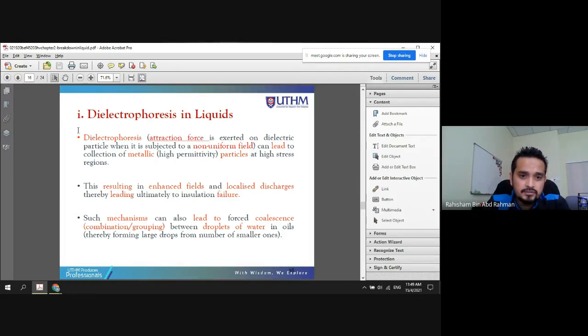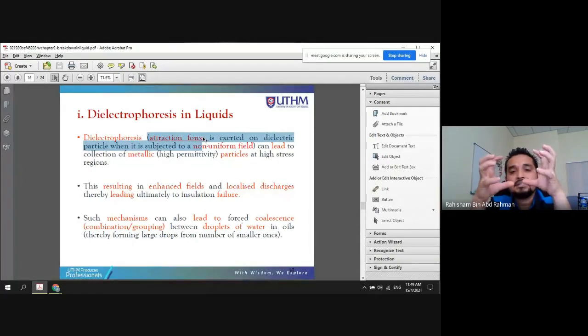Also, due to this force, dielectrophoresis will lead to the formation or combination of water droplets. We have a small gap within the liquid, and this small gap can accumulate due to the attraction force to form a relatively larger void that triggers discharge activity. This localized discharge normally happens at the surface of the electrode where high voltage is applied, as air bubbles or particles move within the liquid and at some point reach that high voltage value, which is where localized discharge normally occurs.